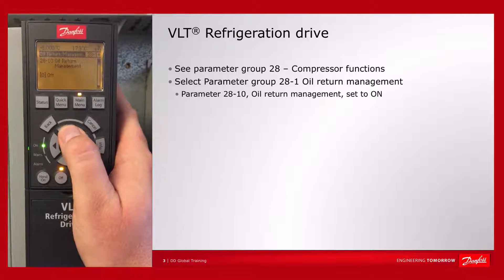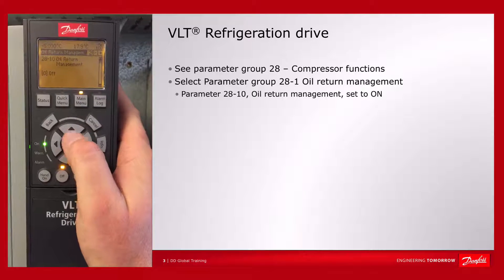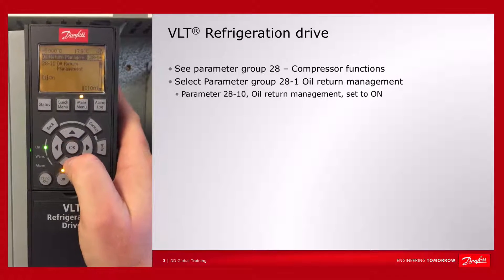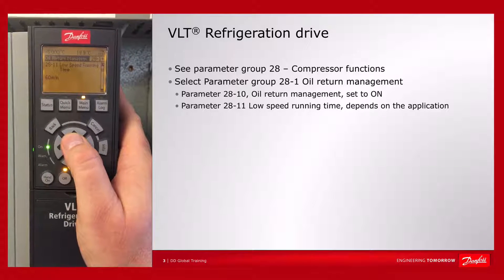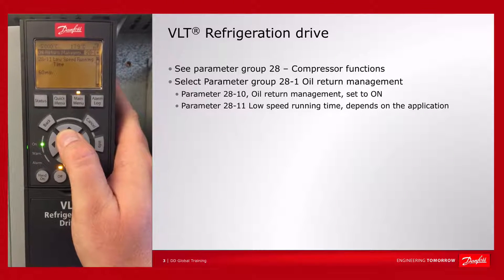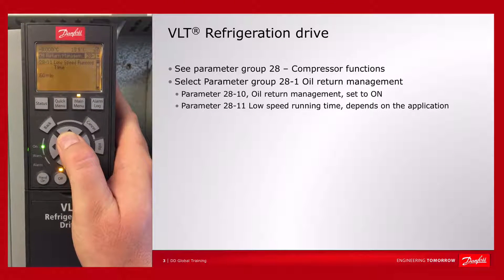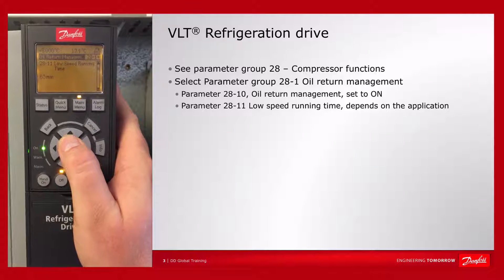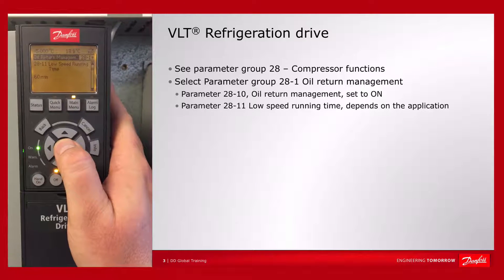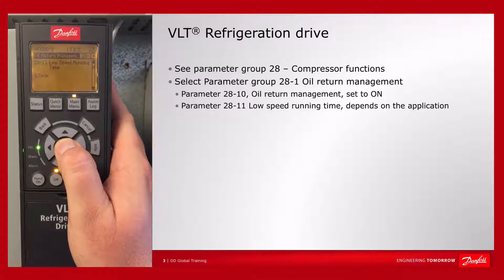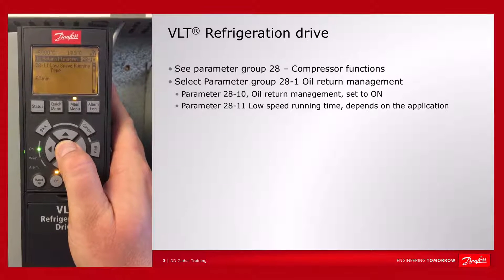The first parameter is 28.10 and you must enable the feature — select on. Then go down to 28.11 where you must determine for how long the compressor should be running at this particularly low speed before it becomes a dangerous situation. This depends very much on the size of the compressor and the system in general, so a general advice cannot be given.